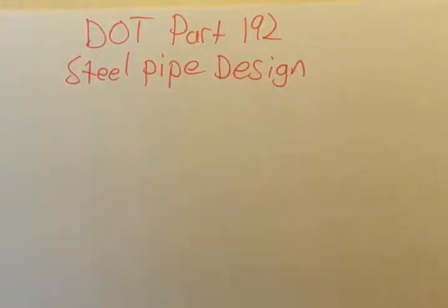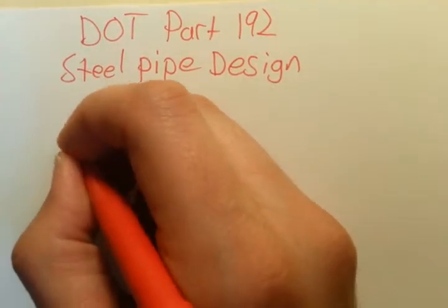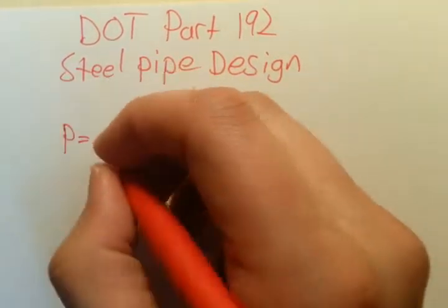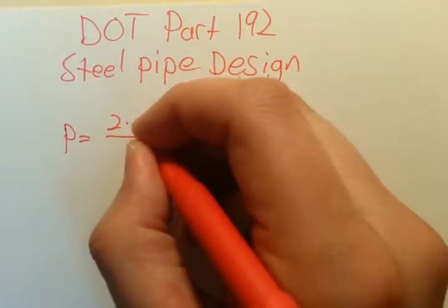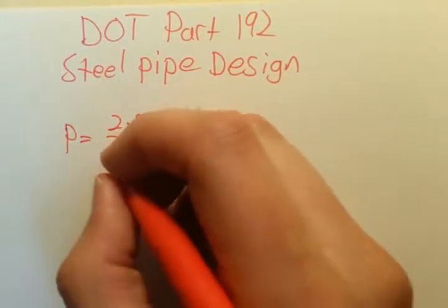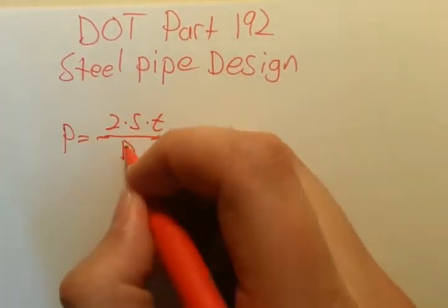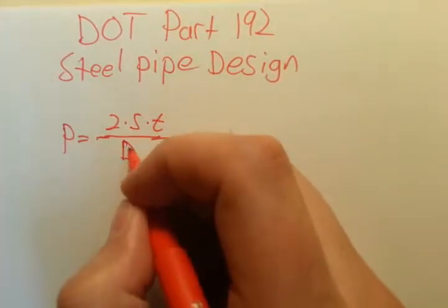Hello guys, welcome to DOT part 192 steel pipe design. We're going to go through the steel pipe design formula found in DOT 192 really quick. So we're going to write the formula: P equals 2 times S, which is yield strength, times T, which is wall thickness, all over capital D, which is outer diameter of the pipe.